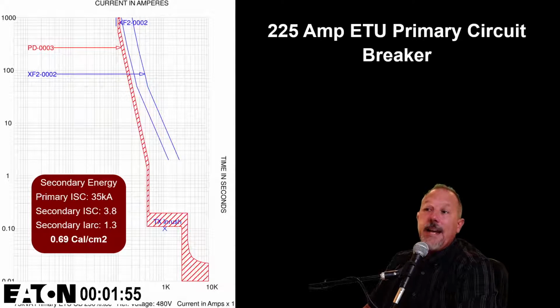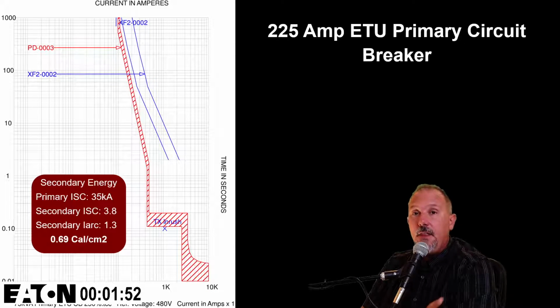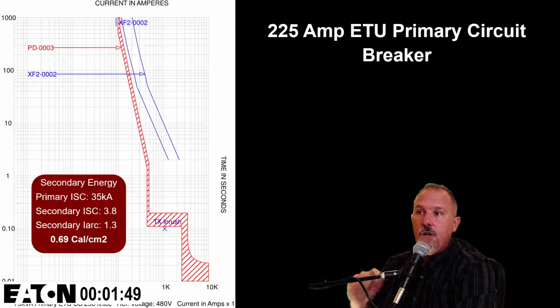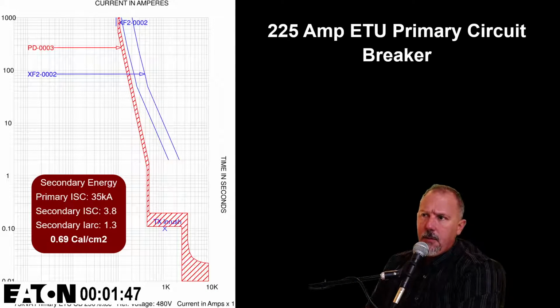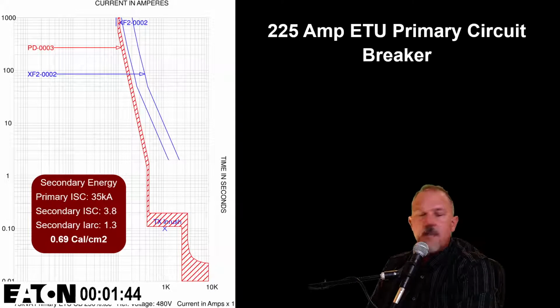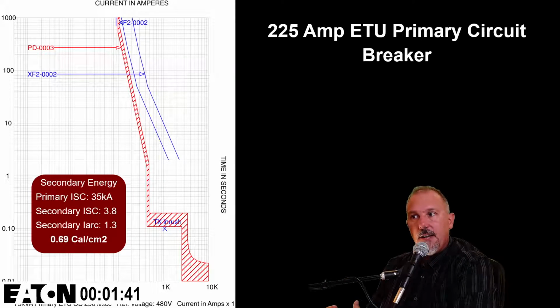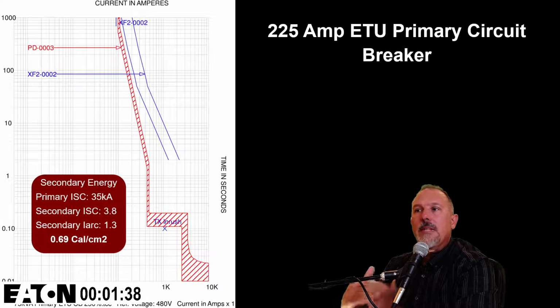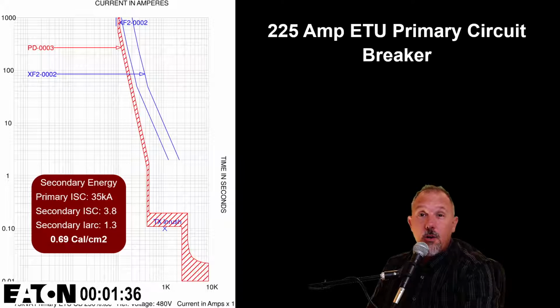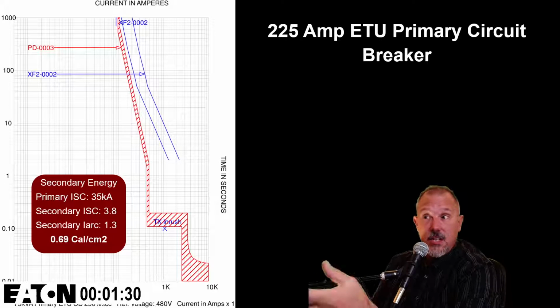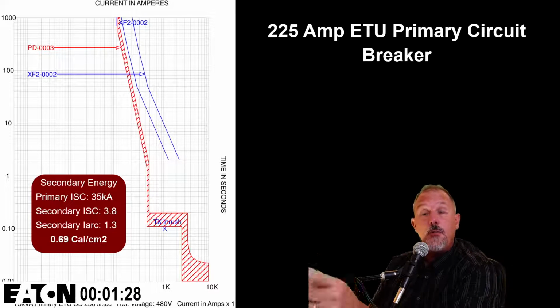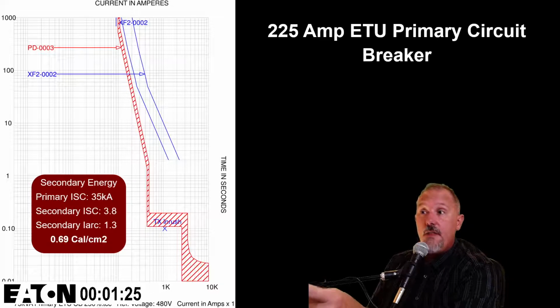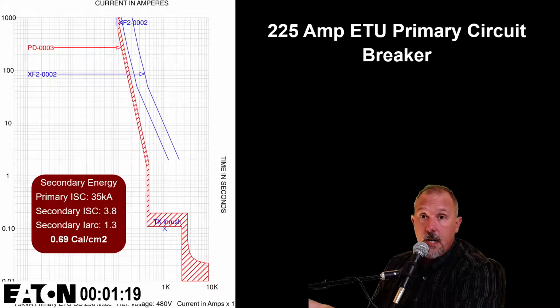1584. When I do this, now I am limiting that secondary arcing current to flow no more than around 0.2 seconds, just about 0.2 seconds. And if I did my incident energy calculation, I can knock that incident energy down to 0.69 calories. Your electrical worker will thank you for that if a problem occurs. So the electronic, and that's just short time delay. Just imagine if you put the arc reduction maintenance technology on that, you'll knock it down less than 0.69. It'll be gone and done, whatever.